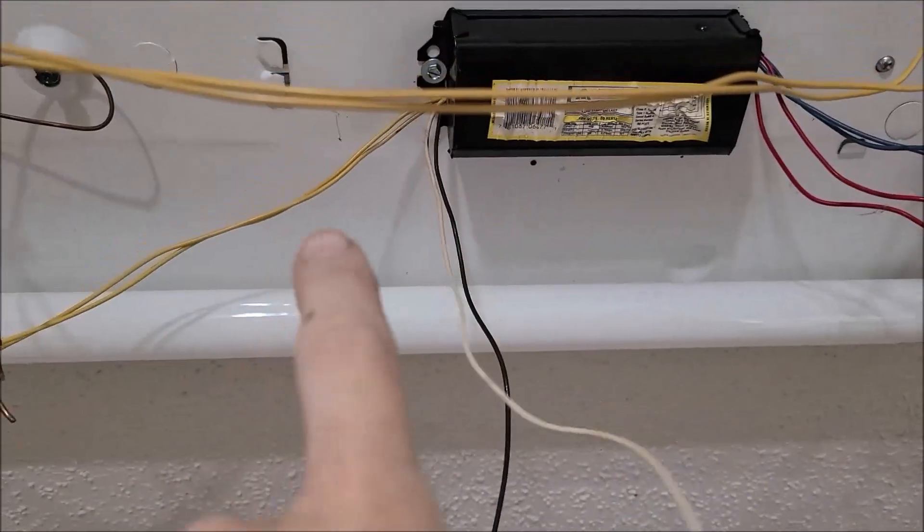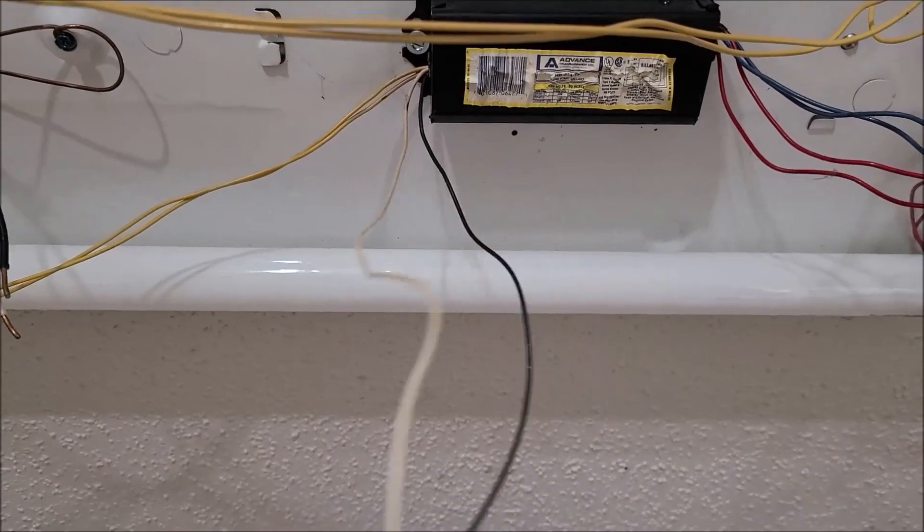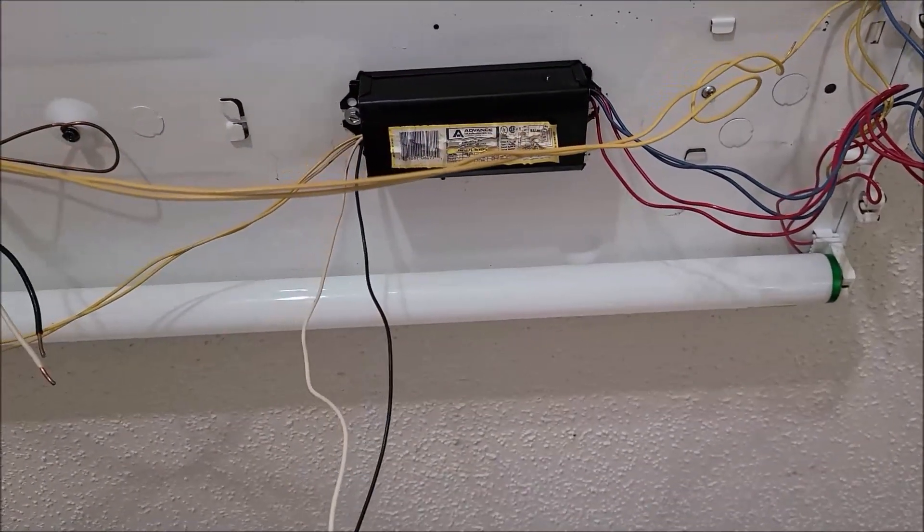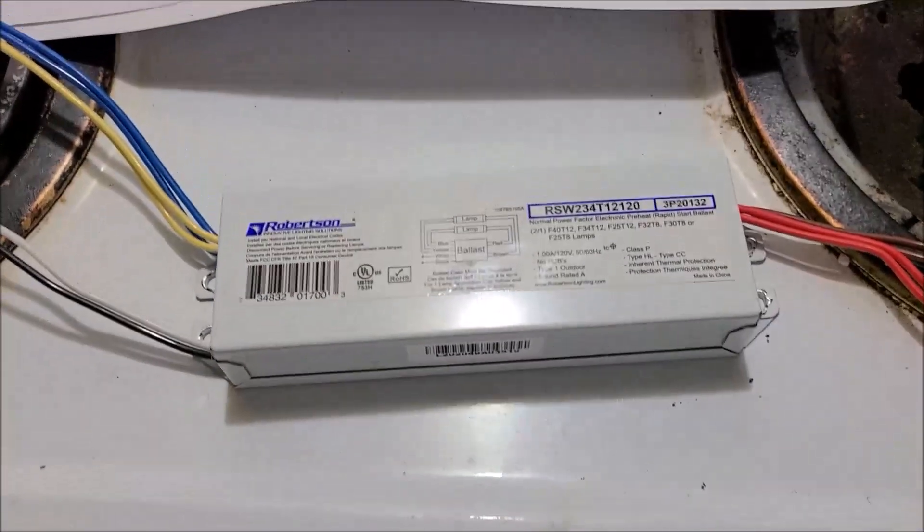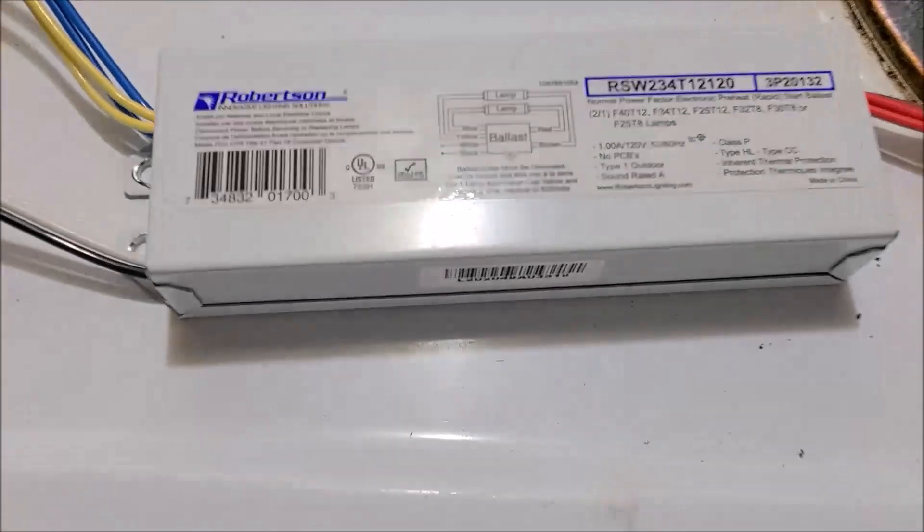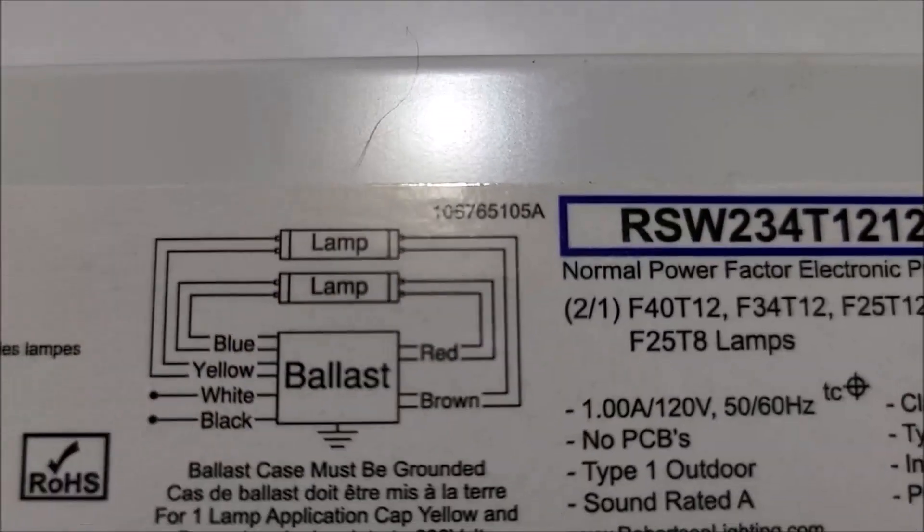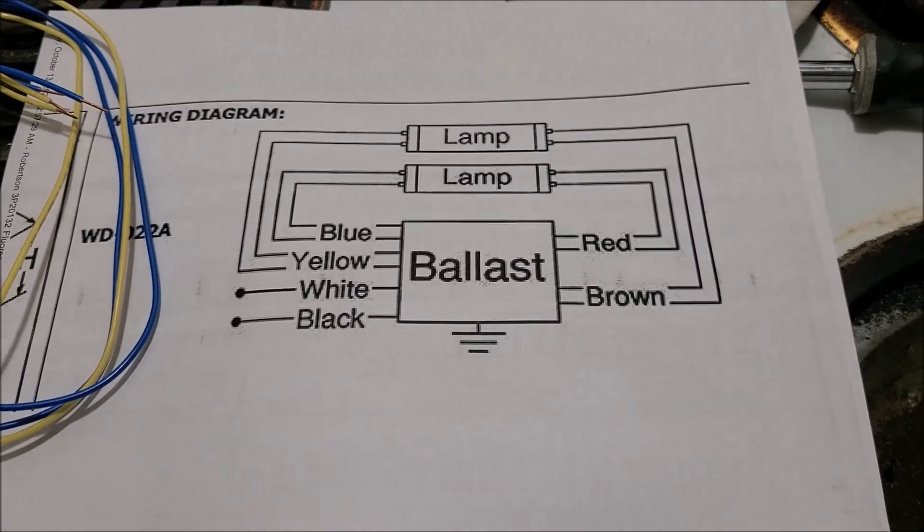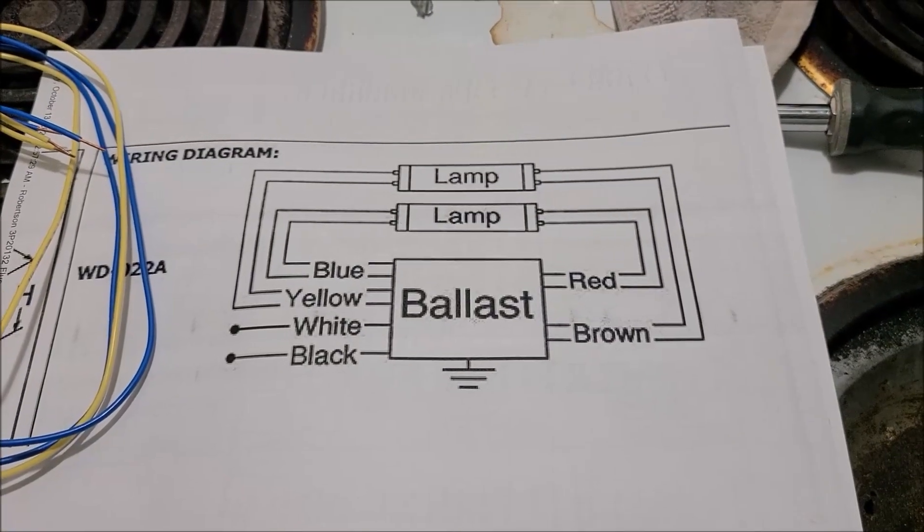But anyway, I got in here looking and you can see we have two wires on this side, we had a power and a neutral wire. We got blue and red, total of eight wires. It's old style, old magnetic ballast. Okay, the new ones being electronic are 10 wires. So first saw that I said, well now how am I going to make this work?